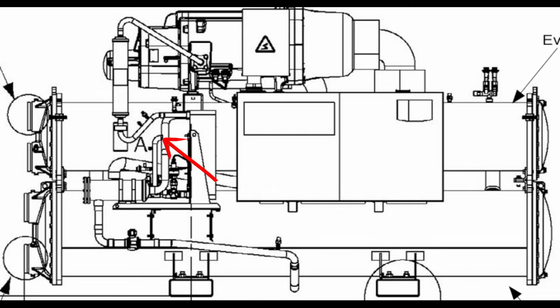The economizer circuit, we can see there's a pipe here. This pipe comes down, feeds into this smaller EXV. This EXV then provides a medium pressure liquid refrigerant that's going to help subcool the primary liquid refrigerant down further. So we're going to increase our subcooling, which helps get our enthalpy lower on that liquid refrigerant. And then this is going to flash off out of the evaporator and up into this.